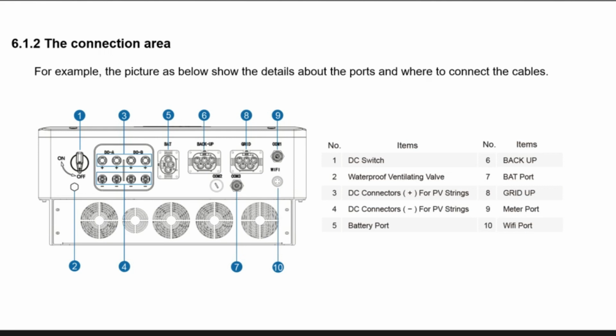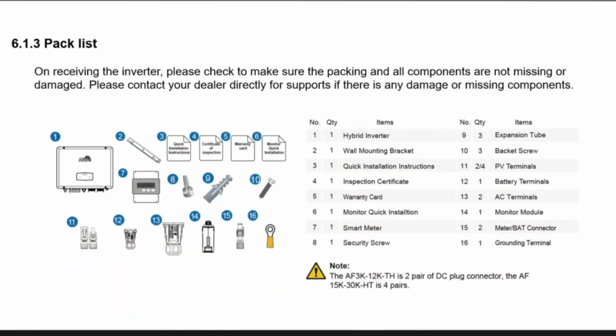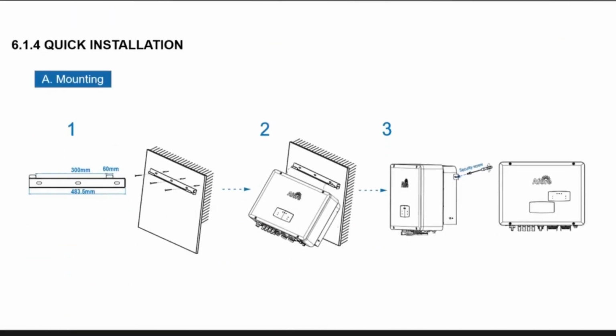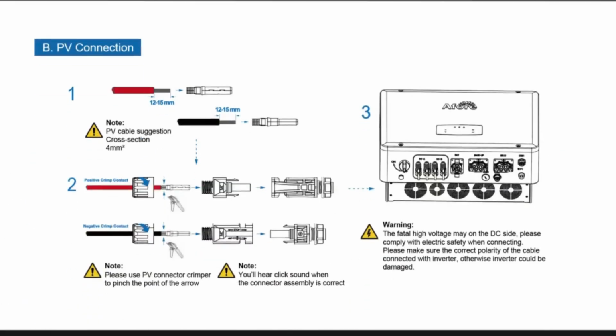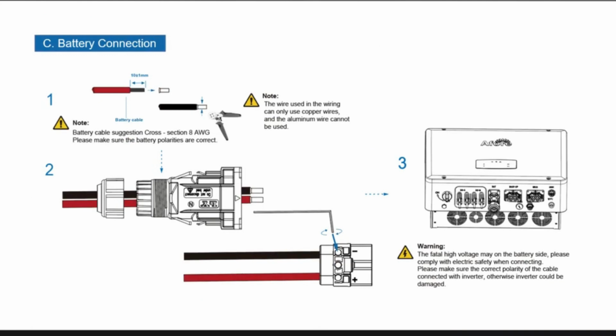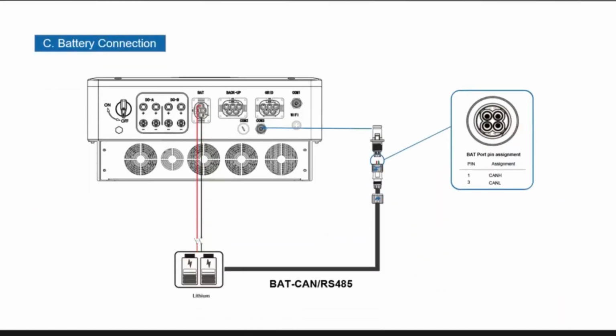This gives you the dimensions of the 3-phase hybrid inverter. And obviously this is the same again. This comes with all of the cables and connections that you actually need for the connection of the complete system. It shows you the connection for your solar input that you put into the inverter, and the battery connections into the bottom of the inverter. Same again on here: the positive faces towards you and the negative is at the back. So provided that they're that way round, you know that you've always got the connections the right way round.